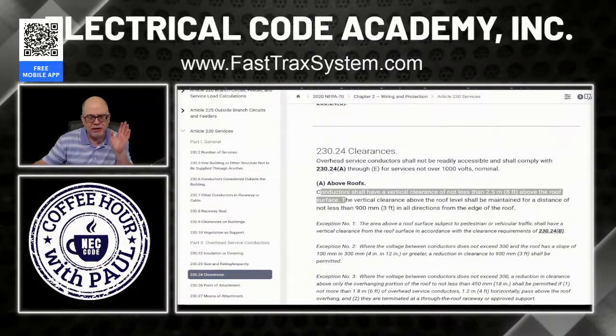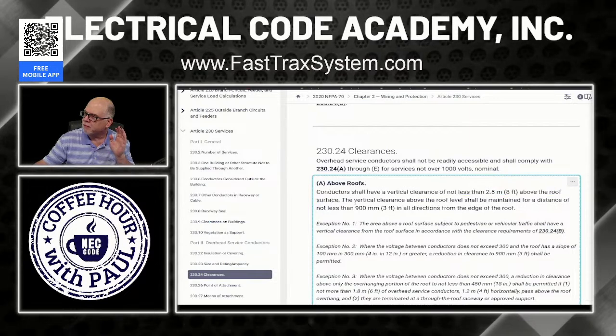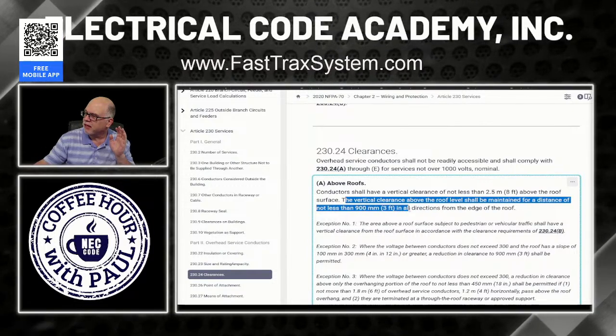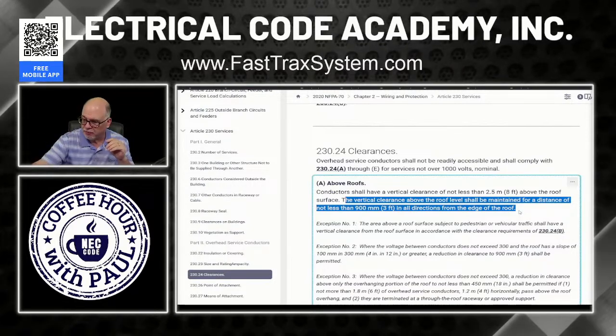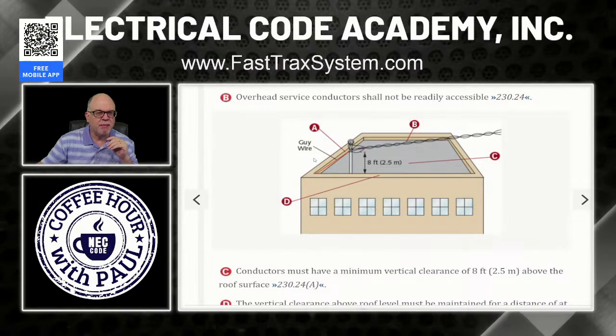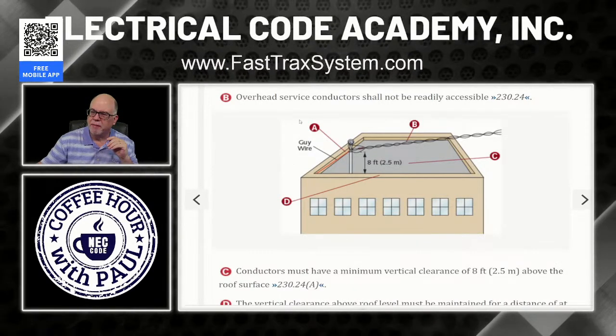Let's go back. Again, we're going to dissect these things right here. So we stopped at that 8 foot. But here is where it said the vertical clearance above the roof shall be maintained for a distance of at least 3 feet in all directions from the edge of the roof. Okay. So what does that mean for us? Well, this 8 feet, by the way, comes out 3 feet. Right here. See my mouse right here? It comes out 3 feet, then up 8 feet.